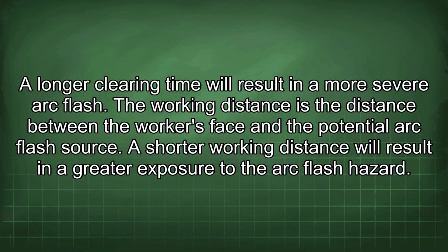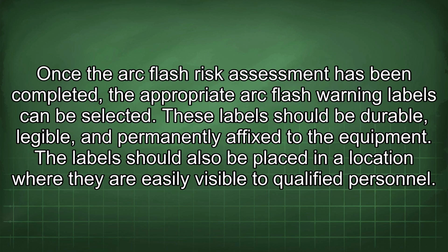The working distance is the distance between the worker's face and the potential arc flash source. A shorter working distance will result in a greater exposure to the arc flash hazard. Once the arc flash risk assessment has been completed, the appropriate arc flash warning labels can be selected. These labels should be durable, legible, and permanently affixed to the equipment. The labels should also be placed in a location where they are easily visible to qualified personnel.